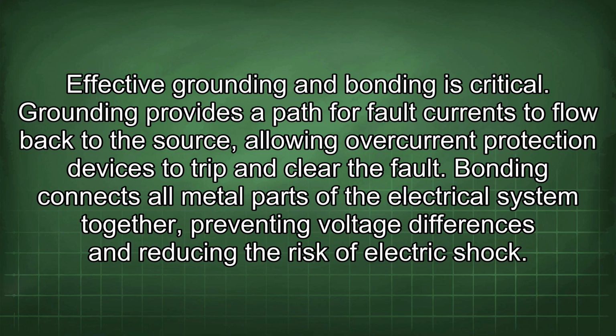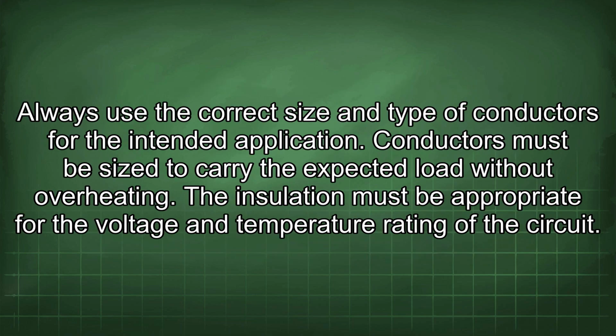Grounding provides a path for fault currents to flow back to the source, allowing overcurrent protection devices to trip and clear the fault. Bonding connects all metal parts of the electrical system together, preventing voltage differences and reducing the risk of electric shock. Always use the correct size and type of conductors for the intended application.